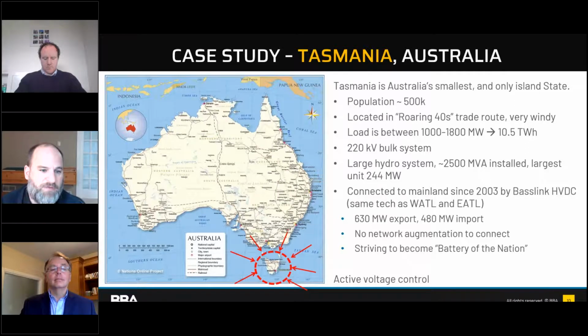So what does that mean? It means that when you're at high load and Basslink's pushing out, you're in that weird part of the regulation curve. That's why we were seeing cases when Basslink first went live where 50 megawatts could cause a 6 or 7% voltage variation. So there were ramp rate limitations on Basslink, and it wasn't able to pursue prices because of the inability of the Tasmanian transmission network to control the voltage.